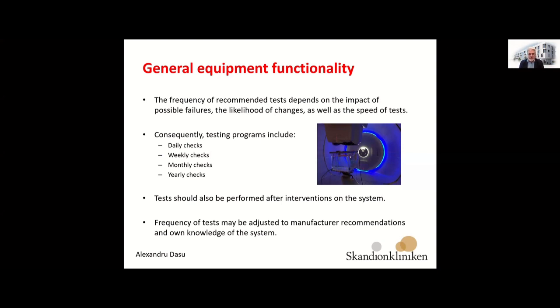Now, the testing program for the general equipment functionality is usually divided into daily, weekly, monthly, and yearly checks. But in addition to these program checks, tests should also be performed after interventions on the system, because depending on the intervention, the output or the performance of the system might be affected. And if you remember from the very beginning, it is the responsibility of the medical physicist to ensure that there is a high quality in the delivered dose.